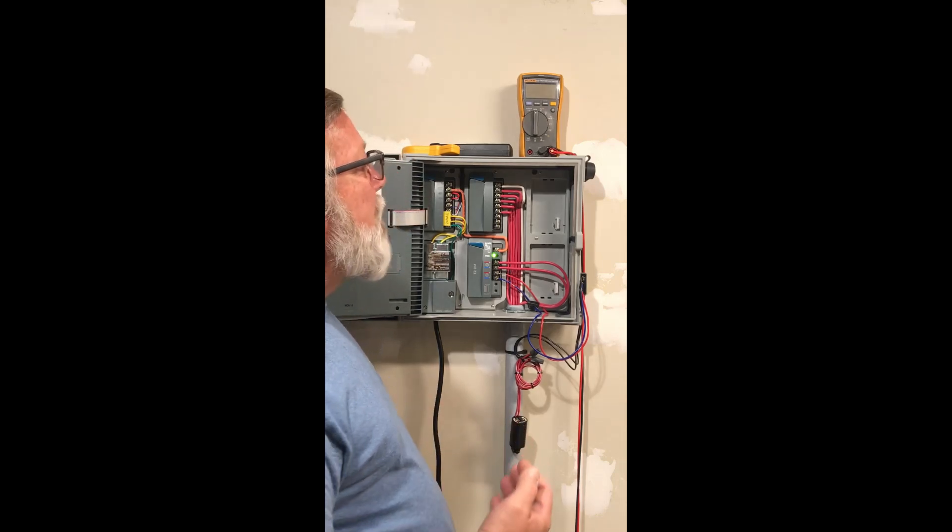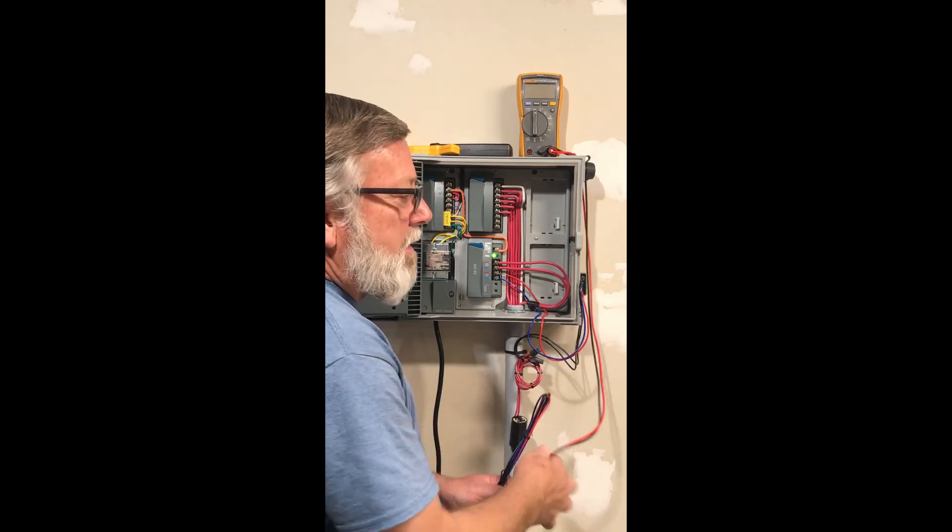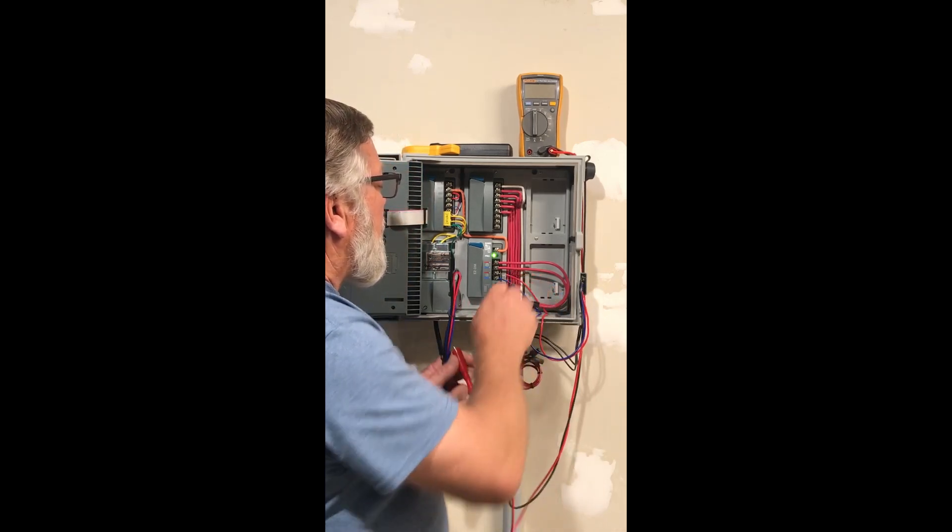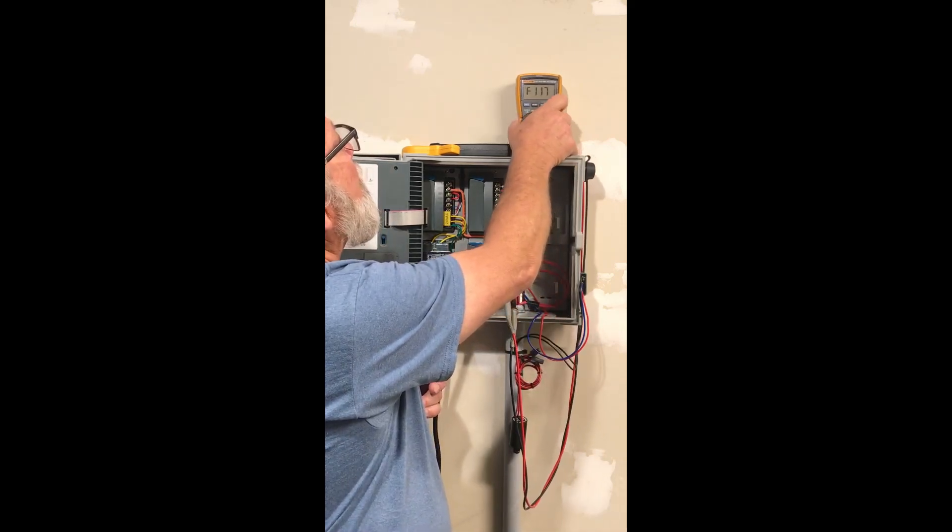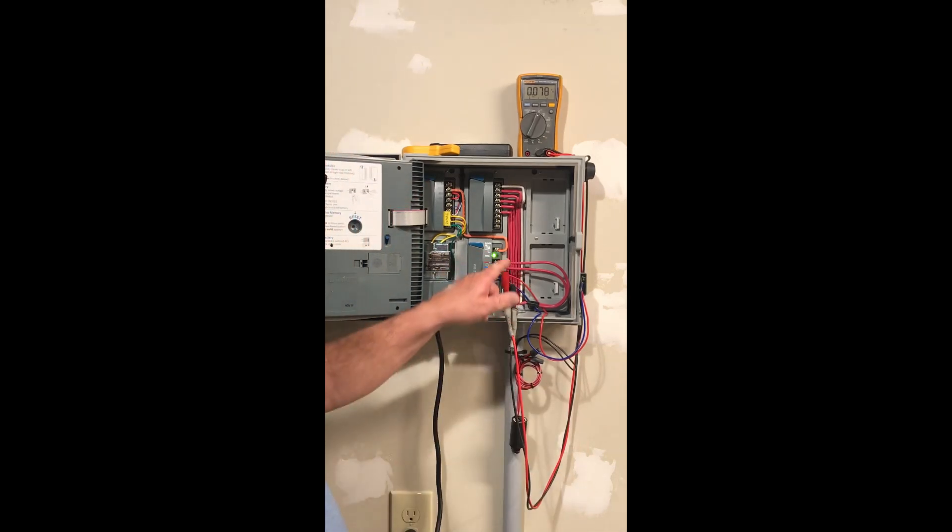It's easy to diagnose if you have any problems. Right now this two-wire path should have no voltage on it. There's nothing on. It's just sitting here waiting to go and if you take a look at my voltmeter, you should see it reading basically zero volts. There is no voltage on here so right now it's at 0.078 volts. So there's no voltage on here even though the green light is on. This green light here is just telling me that this module right here has power to it and it's ready to go.